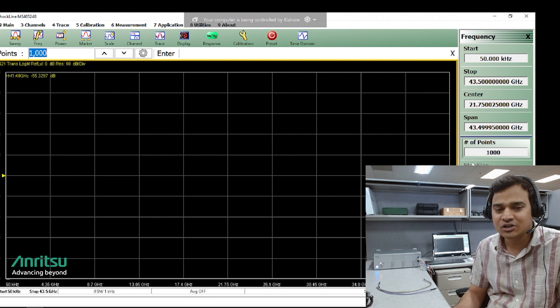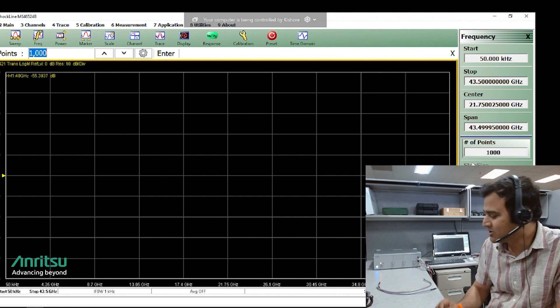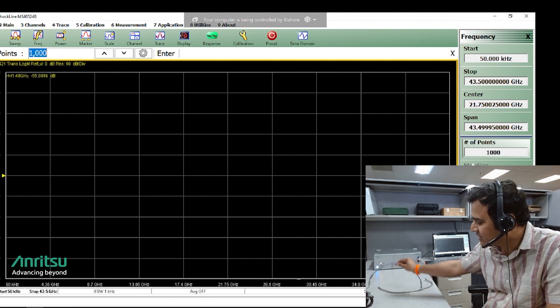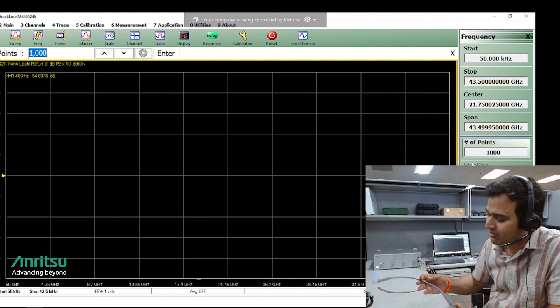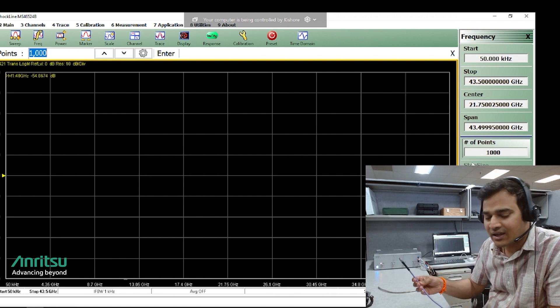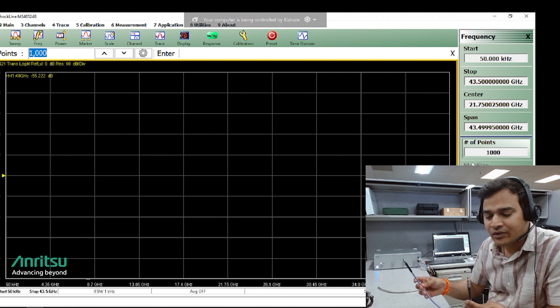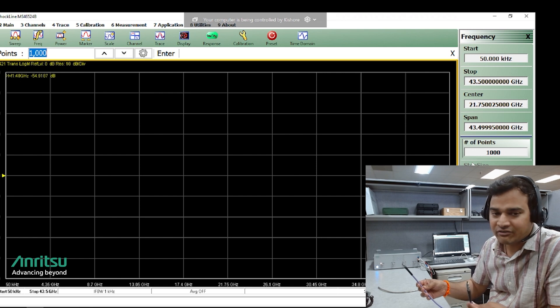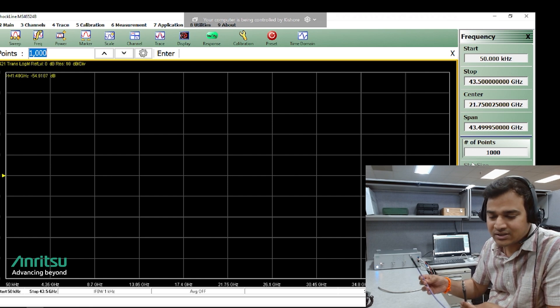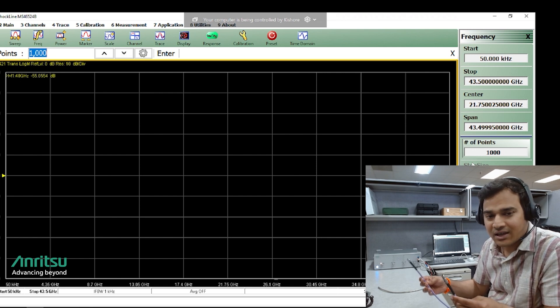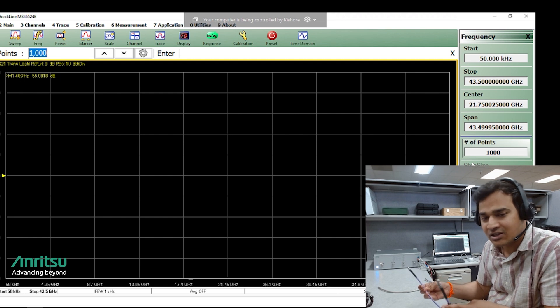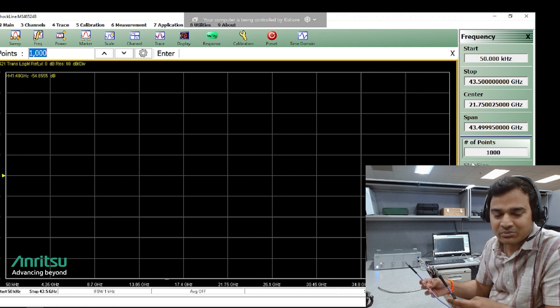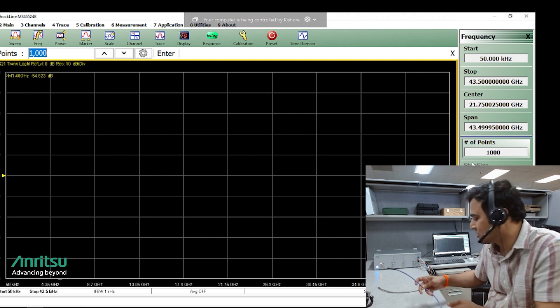Procedure is very simple. Before measuring the DUT we will need another coax cable which I will refer to as a cal cable. We will do the TFR cal using this cal cable. Once cal is done I will insert the DUT cable and measure the parameters. Let's go through the measurements now.